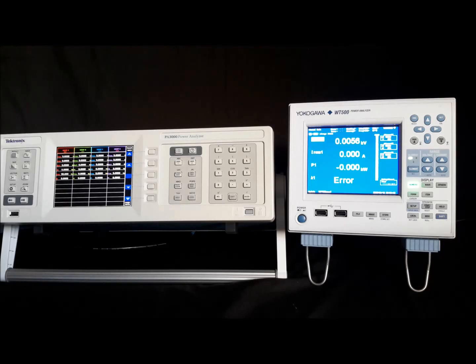So what do we get for our money? First, the basic specifications show accuracies at 0.05% basic accuracy for the Tektronix, and that's against a 0.1% basic power accuracy on the Yokogawa. Now this may appear to show that the Tektronix is twice as accurate, yet looking further into the specifications, the Tektronix basic accuracy is for voltage and current only, whereas the Yokogawa specification of basic power accuracy is for active power.